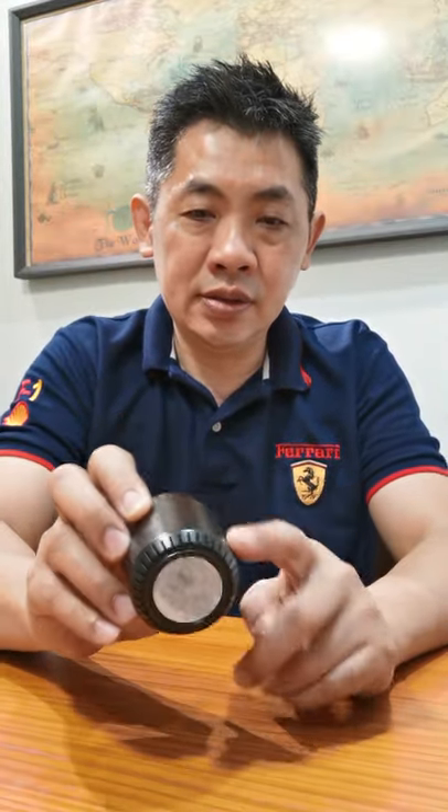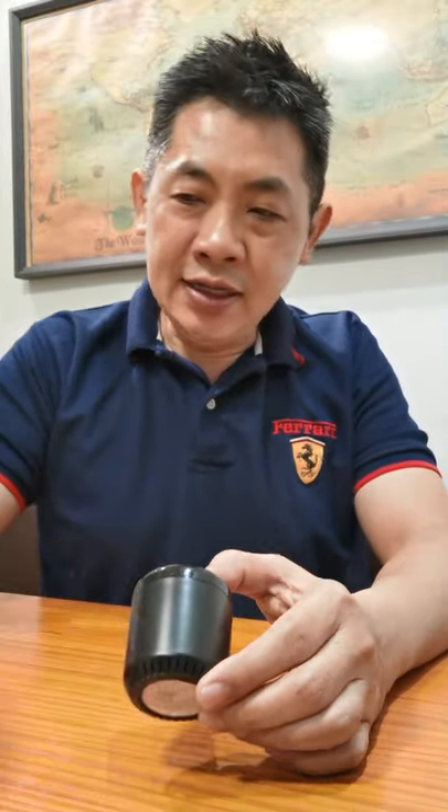The whole fan coil is super wet and it wraps around your blower, constantly discharging cold air and keeping everything wet. I have filmed videos where the blower is wet and the fan coil is extremely wet. Daikin has had a smart solution for a long time — I think since the MA56. You can see this button here that says 'mold proof'.